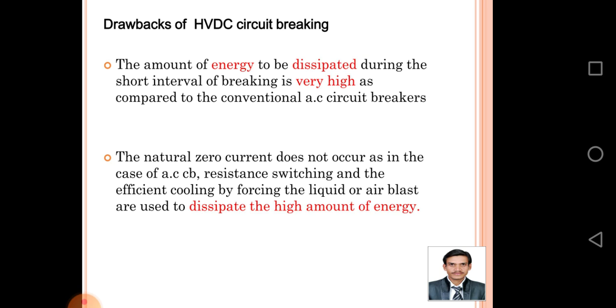The natural zero current does not occur as in the case of AC circuit breakers. Resistance switching and efficient cooling by forcing liquid or air blast are used to dissipate the high amount of energy. This is a simple DC circuit — R is resistance, L is inductance, E is a battery.